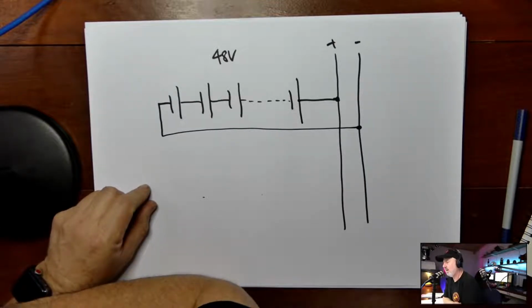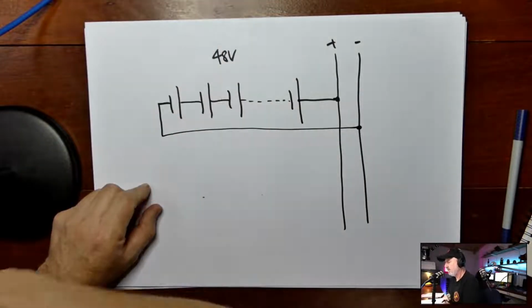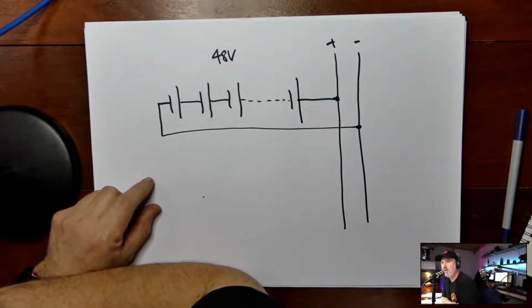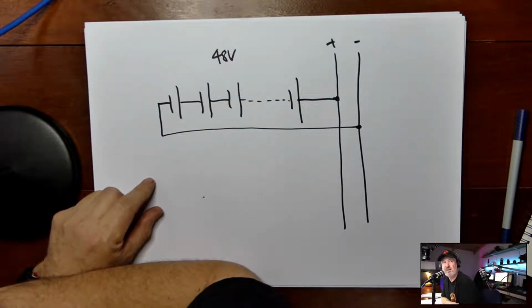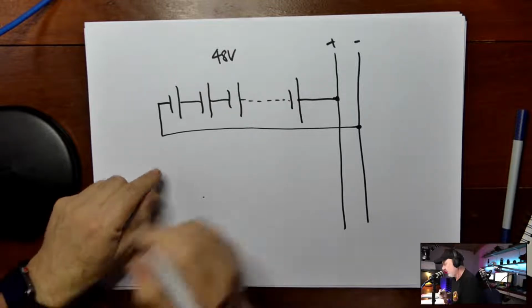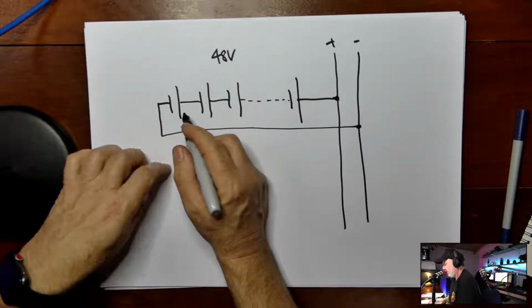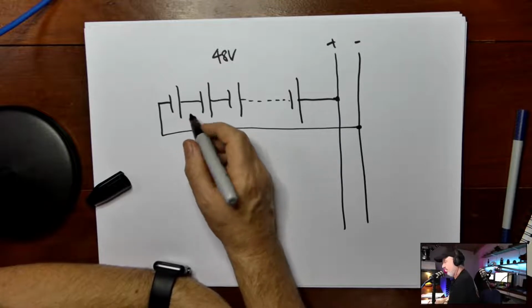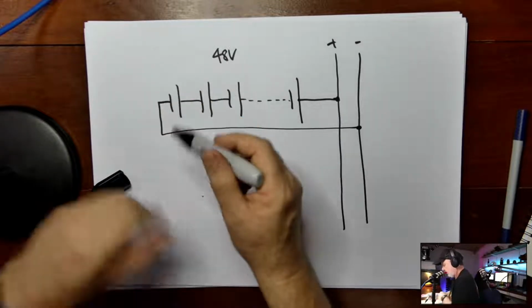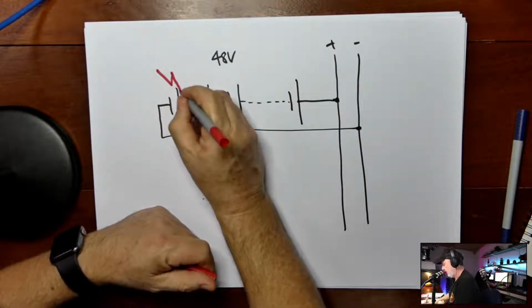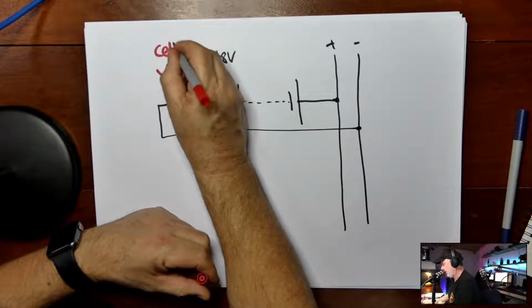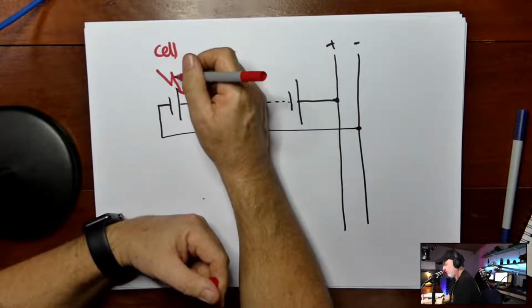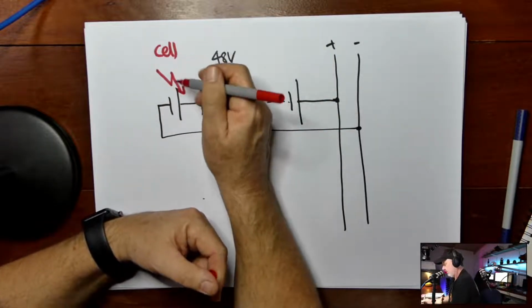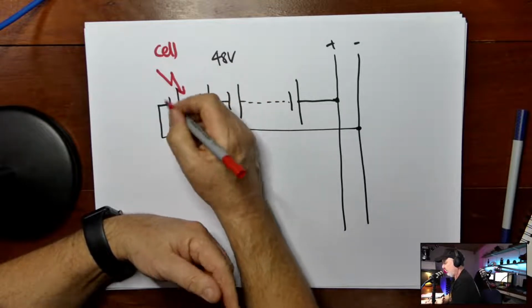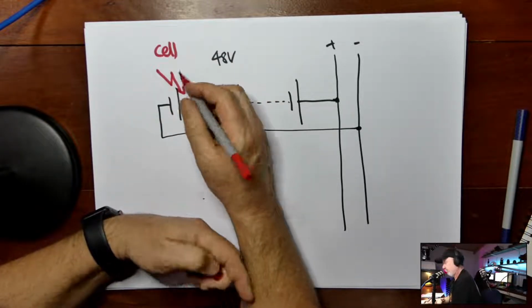So there's my single string. And when I look at this, there's several points that an arc could occur. An arc could occur when those cells are being loaded into the battery rack, for instance. And that would be a fault at this point here, at the cell level. So a cell arc flash incident.